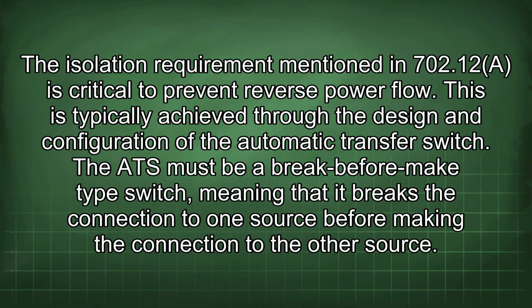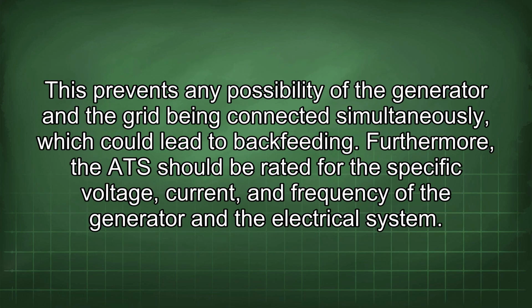The isolation requirement mentioned in 702.12 is critical to prevent reverse power flow. This is typically achieved through the design and configuration of the automatic transfer switch. The ATS must be a break before make type switch, meaning that it breaks the connection to one source before making the connection to the other source. This prevents any possibility of the generator and the grid being connected simultaneously, which could lead to backfeeding.